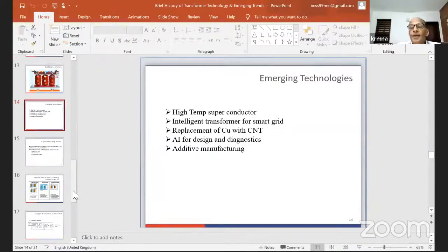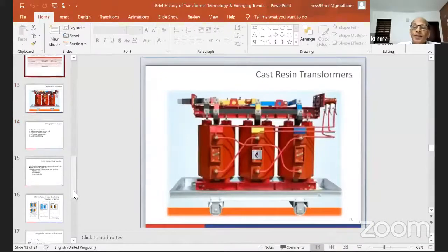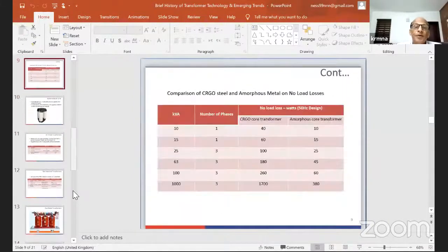Its energy loss is say 0.2 watts per kg or much lower, whereas our normal silicon steel will have 0.6 or more. So it gives losses of like 30-35% of the normal transformer only. I have given a comparison in this slide of some typical transformers with losses of amorphous metal and silicon steel. A simple example is a 100 kVA, which is a very common transformer. With silicon steel, it is around 260 watts, whereas with amorphous metal, it is 60 watts only. So the reduction is enormous.